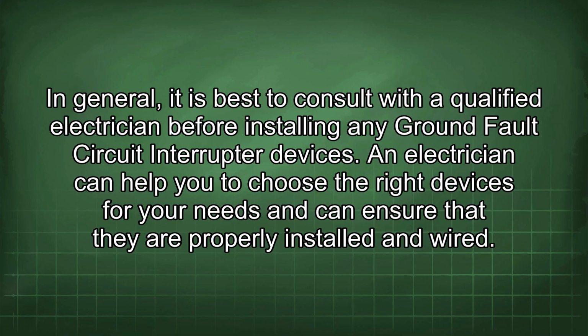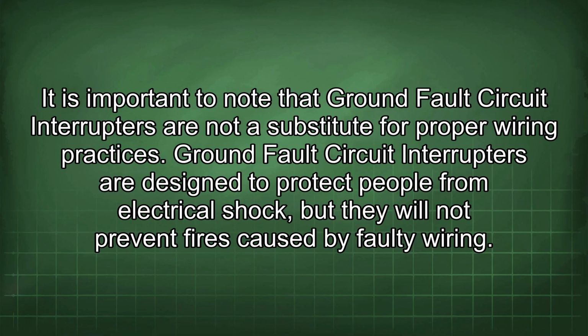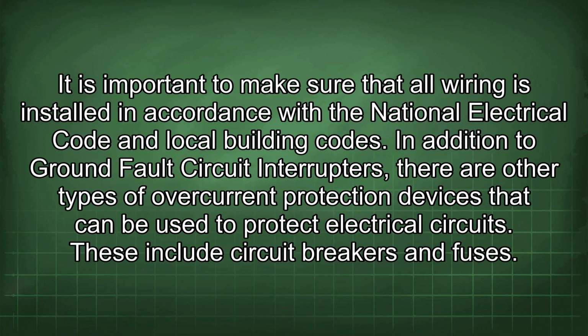It is important to note that ground fault circuit interrupters are not a substitute for proper wiring practices. Ground fault circuit interrupters are designed to protect people from electrical shock, but they will not prevent fires caused by faulty wiring. It is important to make sure that all wiring is installed in accordance with the National Electrical Code and local building codes.